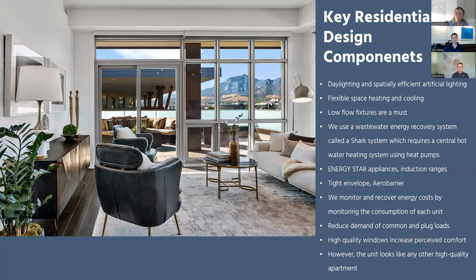The space heating and cooling needs to be a bit more flexible. In an office building, you typically set it and forget it. People like to turn the heat up when it's cold out and down in the summer. So a system that can be flexible for different users is really valuable. The VRF system is good in that way, because you can have some units in heating and some in cooling, and it uses the waste heat generated from cooling to heat the units that are too cold.